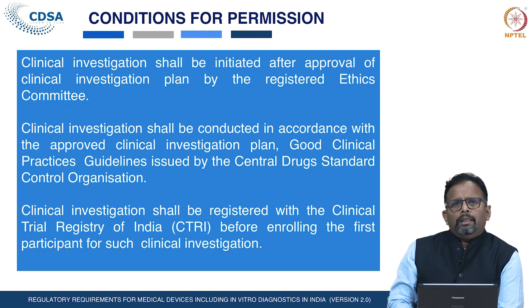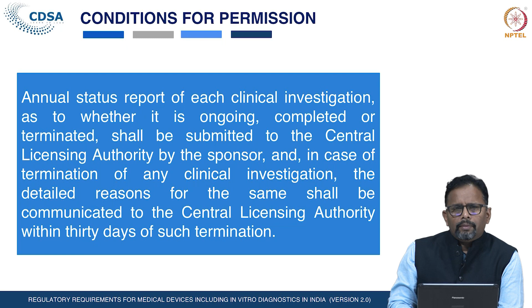Another condition is the annual status report of each clinical investigation, as to whether it is ongoing, completed or terminated, shall be submitted to the Central Licensing Authority by the sponsor. In case of termination of any clinical investigation, the detailed reason shall be communicated to the Central Licensing Authority within a period of 30 days. Information about any unexpected serious adverse event occurring during the clinical investigation has to be submitted to the Central Licensing Authority within 14 days.